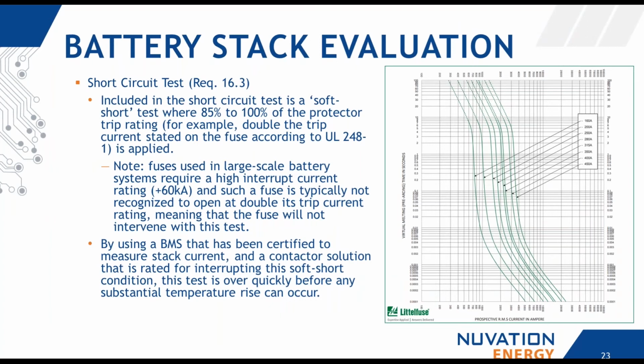Another test I wanted to talk about is a short circuit test. Included in the short circuit test is this concept of a soft short test, where 85 to 100% of the rating is applied. This is the nameplate rating of a fuse. It's not necessarily intuitive that a fuse can't be used to meet a short circuit test, but something to keep in mind is that when you select a fuse for a large scale battery system, typically it needs a very, very high interrupt current, where we're talking about things measured near 100 kiloamps. And such a fuse is not typically recognized to open at double its trip current. That basically means the fuse isn't guaranteed to intervene in this test.